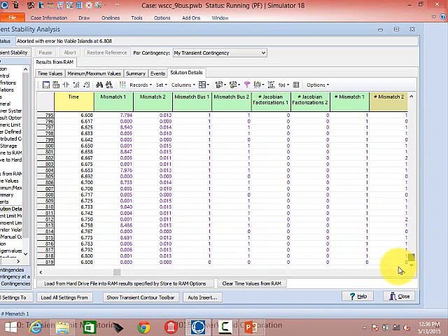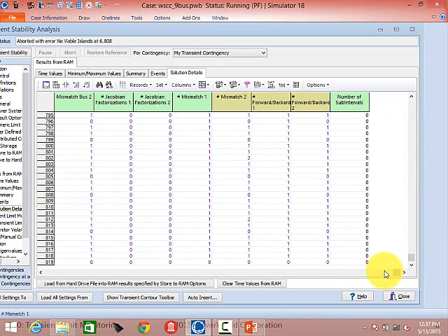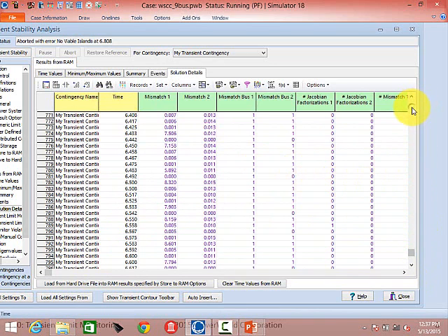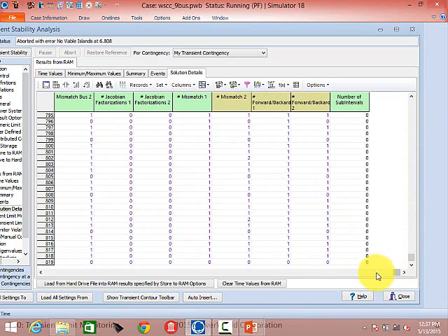Those values on the high and low frequency were originally set to match the TSLF GP1 and GP2 defaults. Oh, okay. And then Jamie changed them on April 13th, 2010. So they haven't been changed in the last 6 months. Okay. No, they were 0.96 per unit, 1.04 per unit, and then he changed them to 0.97 per unit, 1.02 per unit, but he doesn't say why he changed them. I mean, they're just defaults.